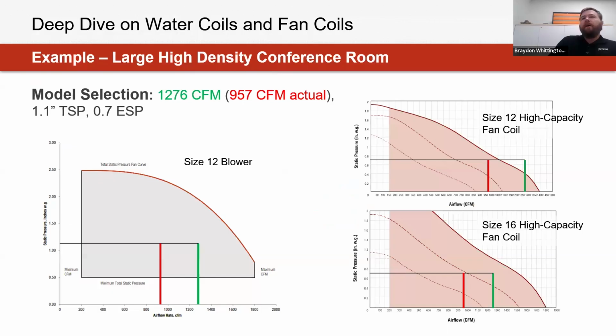And with that, it kind of alluded there to eliminating the commodity style. If we're to look at high capacity fan coils or blower coils, we can then plot these out on their fan curves, and this static pressure mark essentially laying out the external static pressure for that system. I'm noticing this would be a little bit higher for these fan coils on here as well, reflecting around 75% of that curve, for being able to understand where its reference point is going to be for our actual required cooling condition, but then also plotting out our maximum just to make sure that this is even achievable for that fan coil or blower coil that we're plotting it on there too.